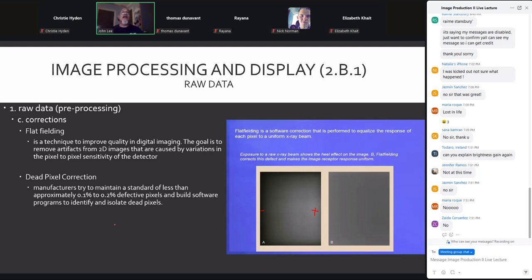Dead pixel correction: the manufacturers try to maintain a standard of less than approximately 0.1% to 0.2% of defective pixels. And their software is utilized to identify and isolate those dead pixels. Once you get above that, the software starts to be challenged a little bit, and some of those pixels will start to appear in your images. Now, 0.1%, 0.2% may not sound like a lot, but on a typical flat panel that has about 9 million detector elements in it, 0.1% of that is 9,000 pixels. 0.2% is 18,000 pixels. That's a lot of pixels.